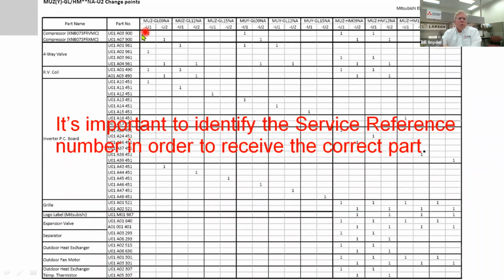The U1 used a different compressor than the U2. The four-way valve is different between the two units. The reversing coil is different. The inverter PC board is different. So it's really critical. You don't just call in and say, I've got a MUZ-GL09 and ask for a part, because we could send you the wrong part.